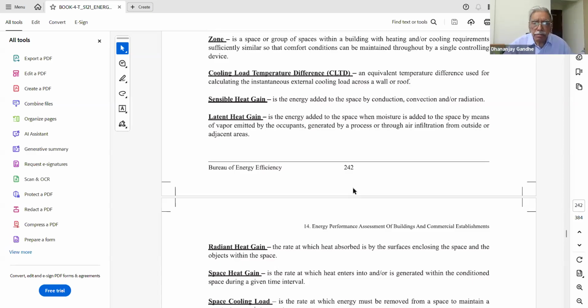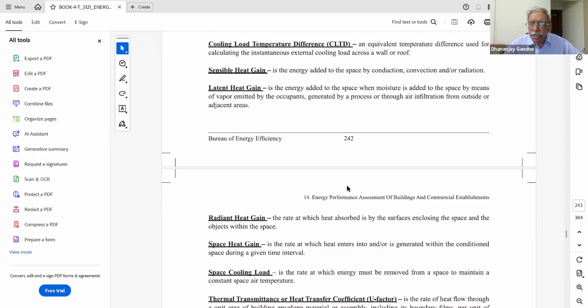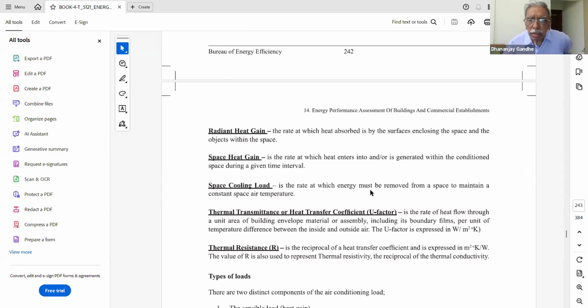What we have seen, just to repeat, there is a term which is called the cooling load temperature difference, CLTD. There is a sensible heat gain from various sources outside as well as internal equipment, etc. Latent heat, for the people who are working, is the heat that goes to add to the heat load, but it doesn't increase the temperature. Sensible heat is the heat that comes in from outside, glass, windows, roof, walls, etc., which increases the temperature inside. So that is the sensible heat. So we have to calculate all this. These calculations are given. We have seen it, but we will repeat it again.